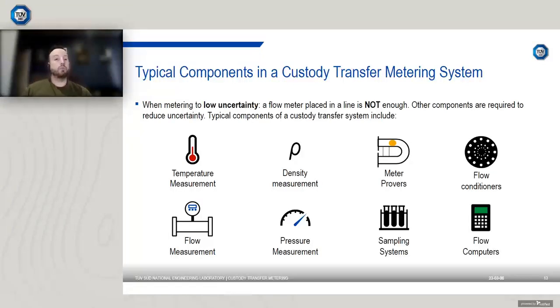So, if you want to achieve a low uncertainty, it's not enough to simply place a flow meter in a line. Other components are required in order to meet those uncertainty targets. So, typical components in a custody transfer system obviously include flow measurement, but you've also got things like temperature and pressure measurement, which are critical for things like determining fluid properties. Density measurement is also important, depending on the metering technology that you're using. Meter provers are quite important to verify the performance of your flow measurement system.